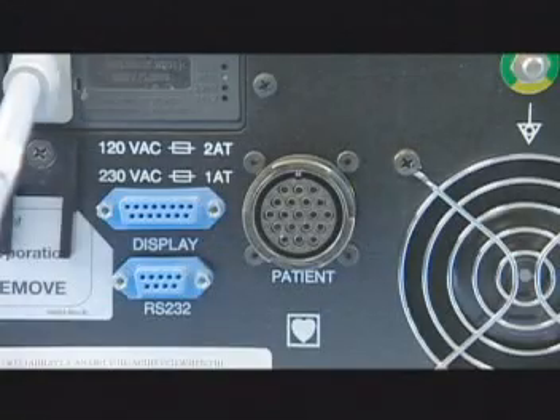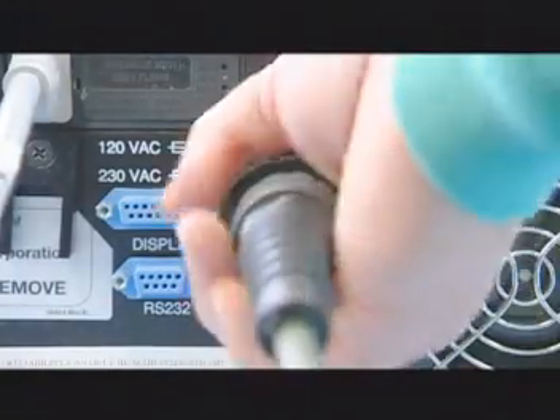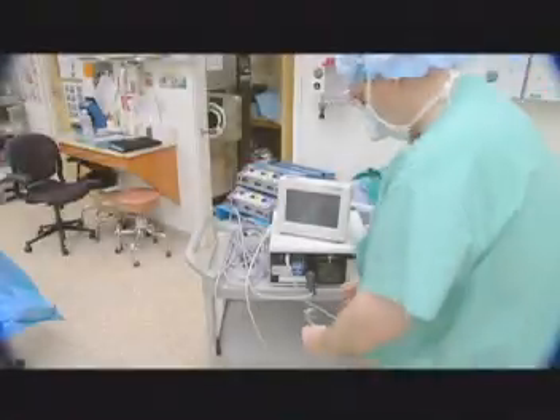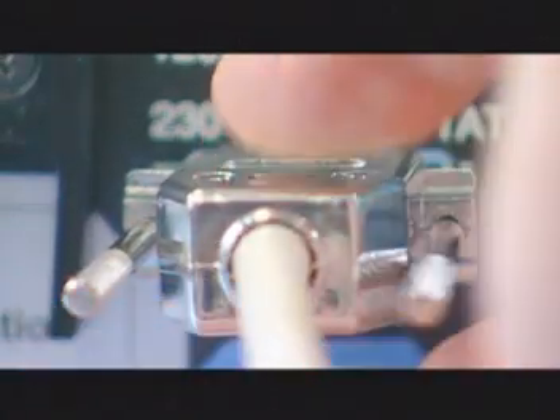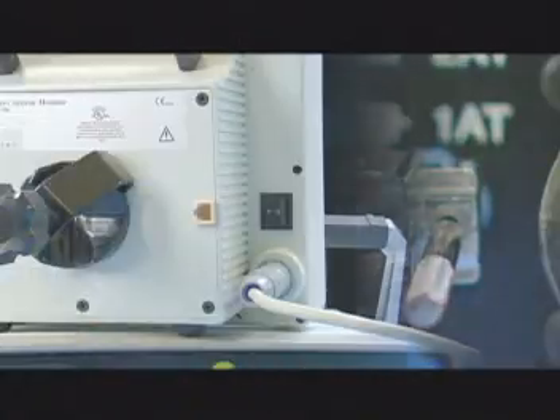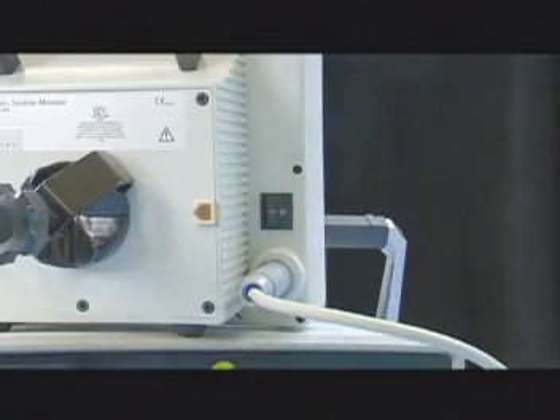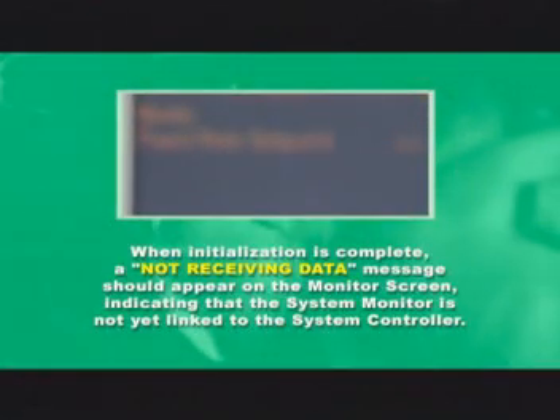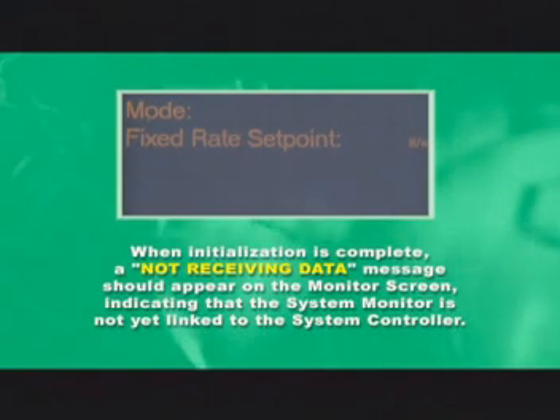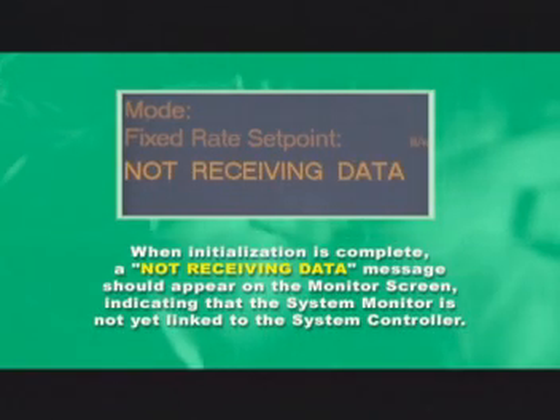Next, plug the large barrel connector on the PBU cable into the back of the PBU. Then connect the system monitor's beige control cable to the display connector located on the back panel of the PBU. The system monitor may then be turned on as well. Note, when initialization is complete, a "not receiving data" message should appear on the monitor screen, indicating that the system monitor is not yet linked to the system controller.